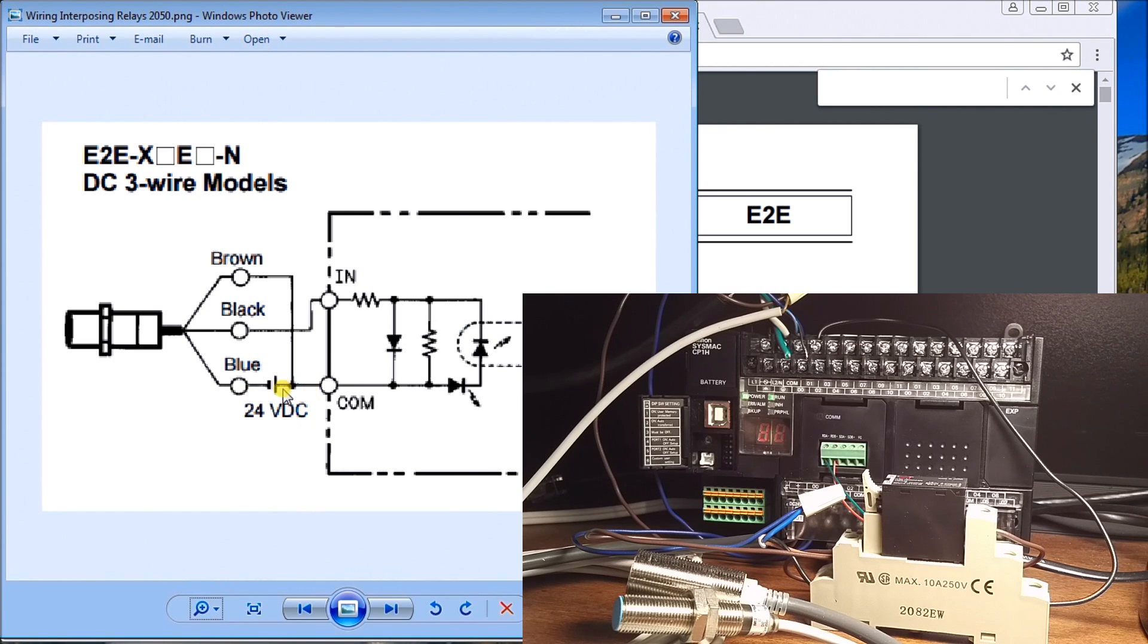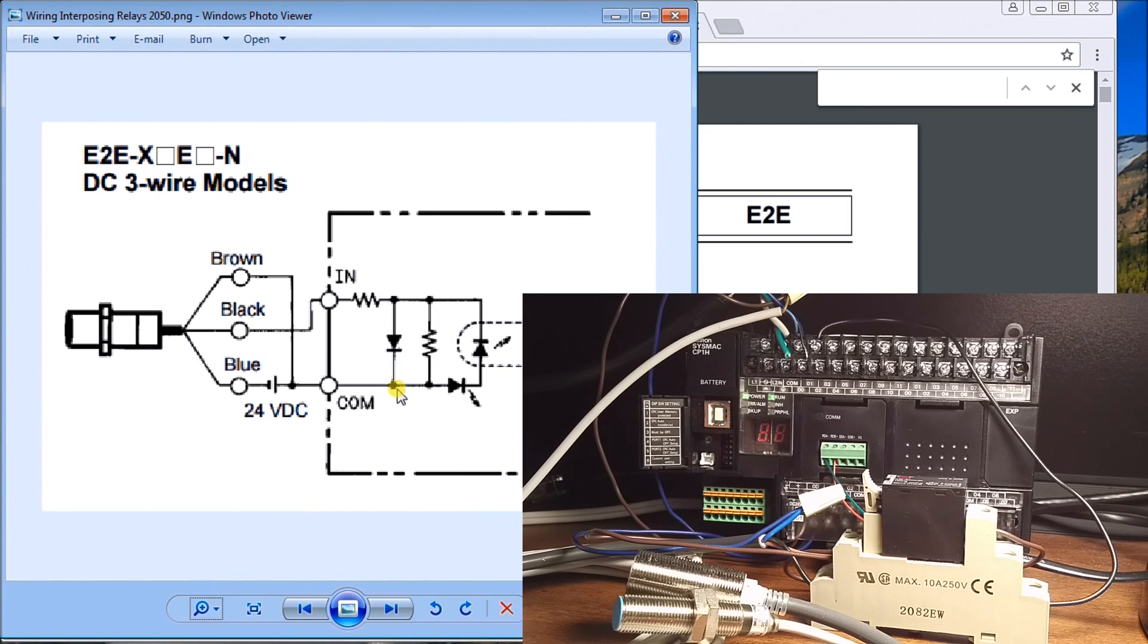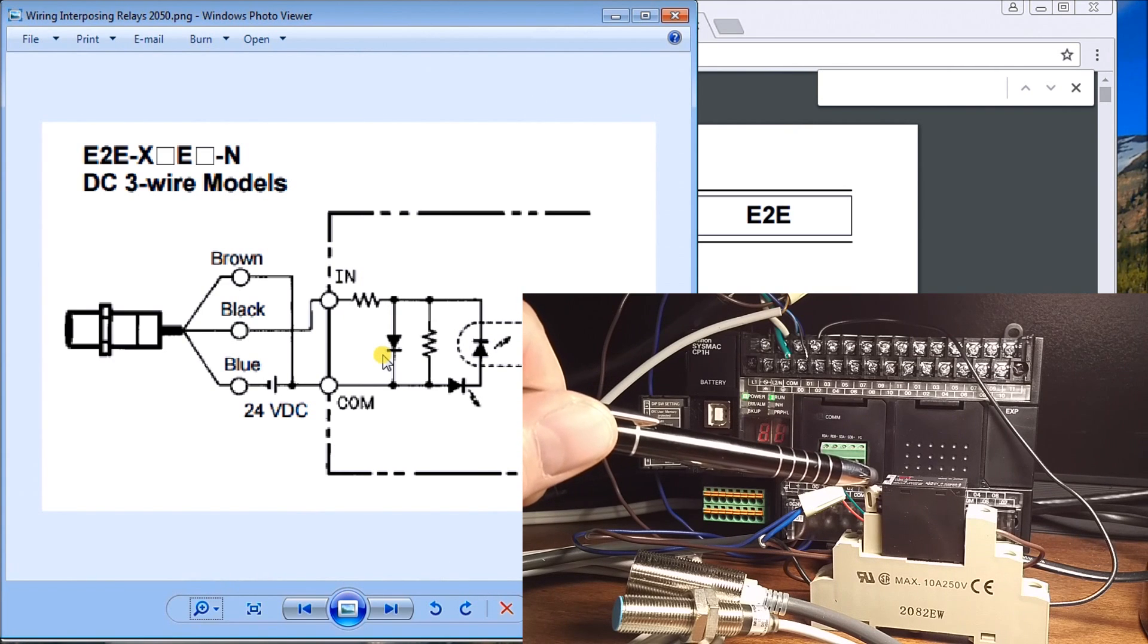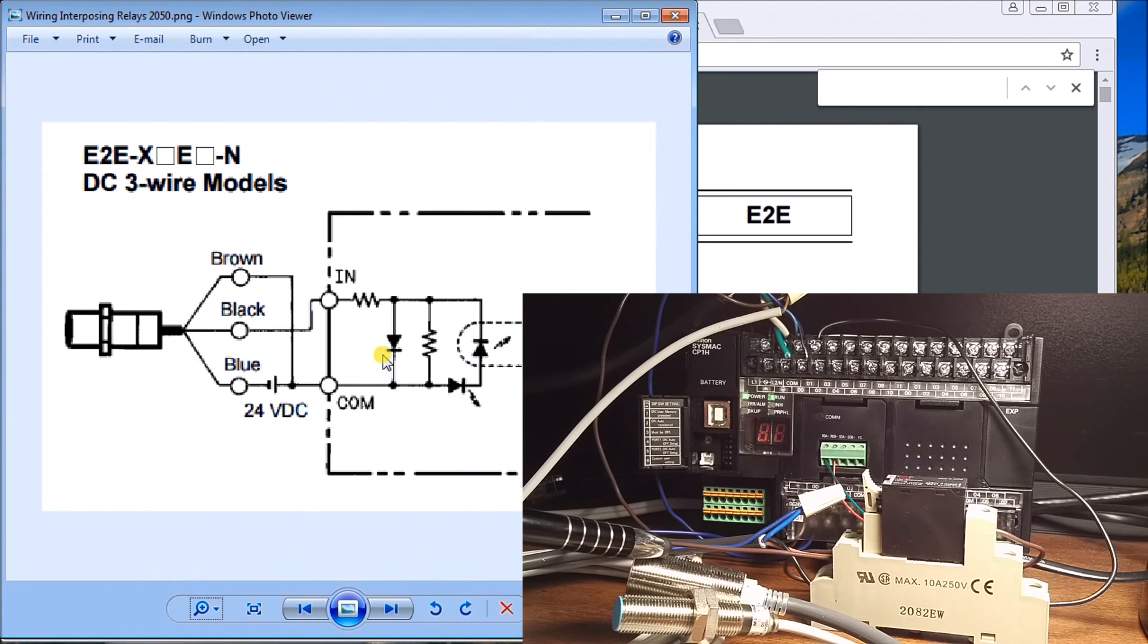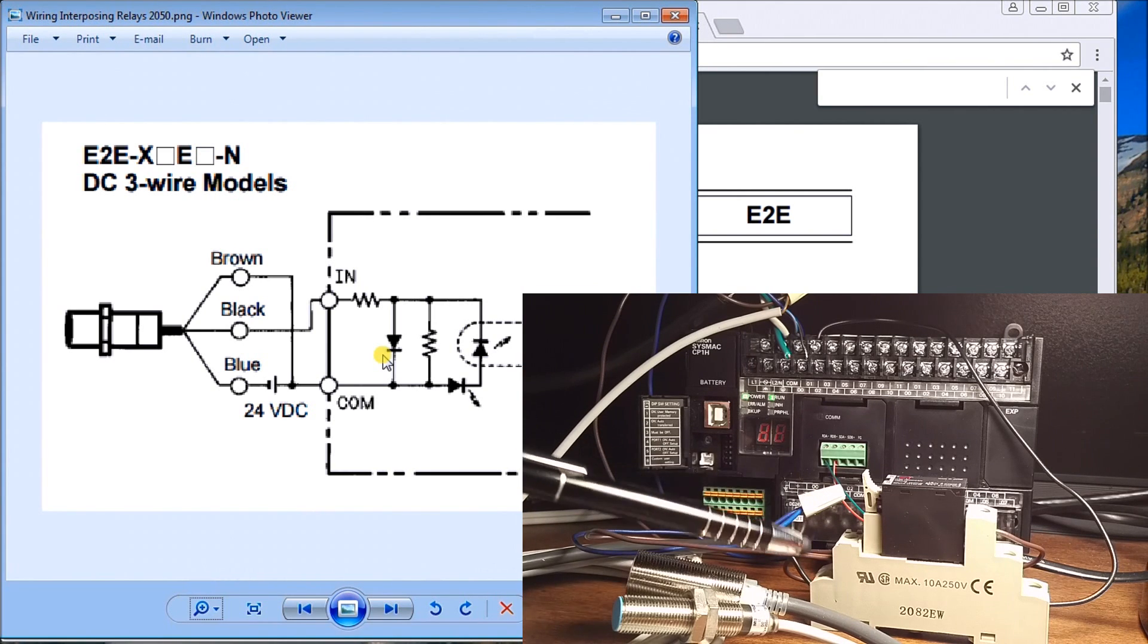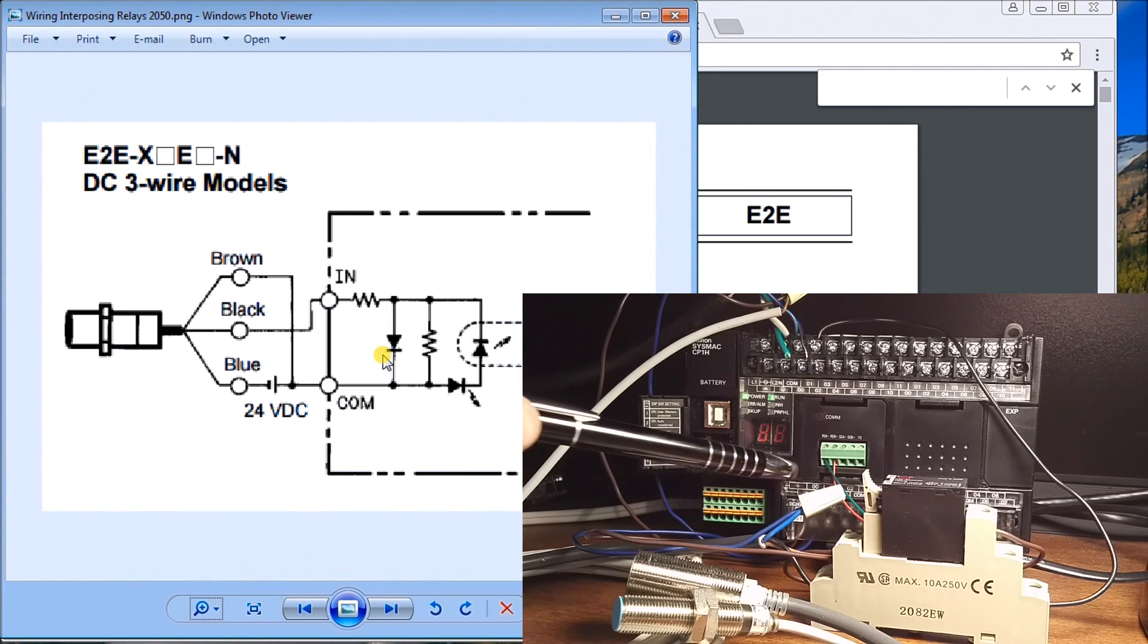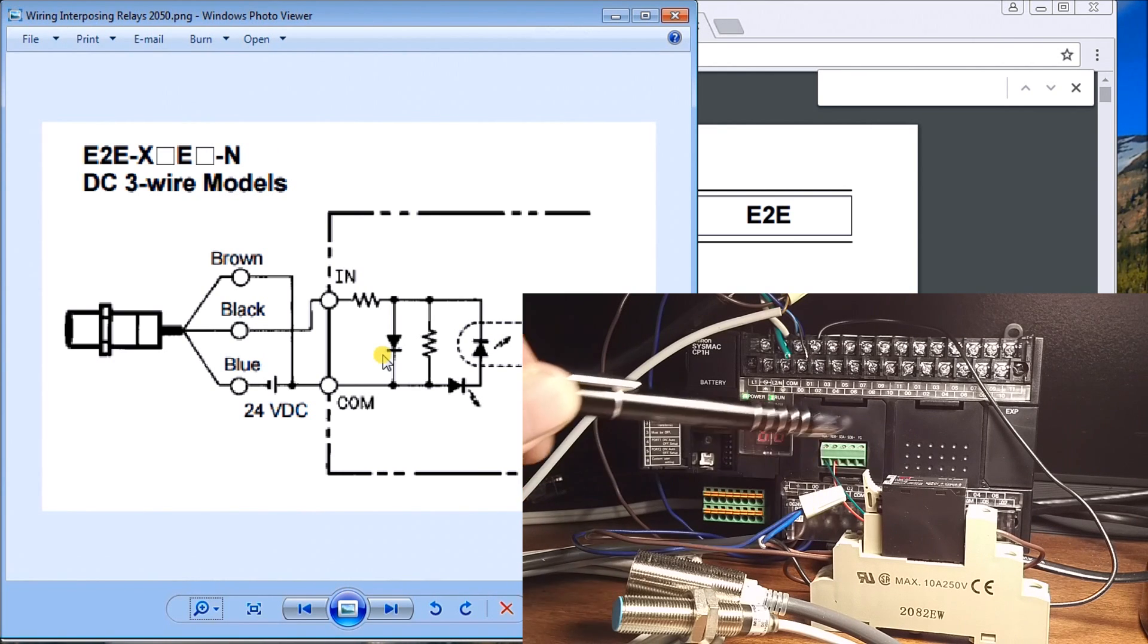Because of that, we'll use the coil of our interposing relay as the load. Here's my Omron NPN wired into the coil of this relay. My black wire and my brown wire is where the load appears, and my blue wire is connected together to energize this coil.